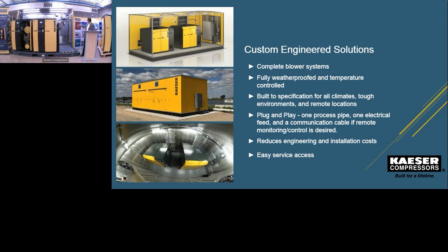Of course, we have power. You can't quite see it, but behind me there is a disconnect on the outside. This is where you bring your 3-phase power. It comes into a distribution box, which has a series of breakers on it, breakers for the blowers, breakers for the 115 volt to power things such as lights and fans, as well as louvers. So you can see here the system includes everything that you would need for a station that you might have in a room. It comes already packaged and ready to operate.